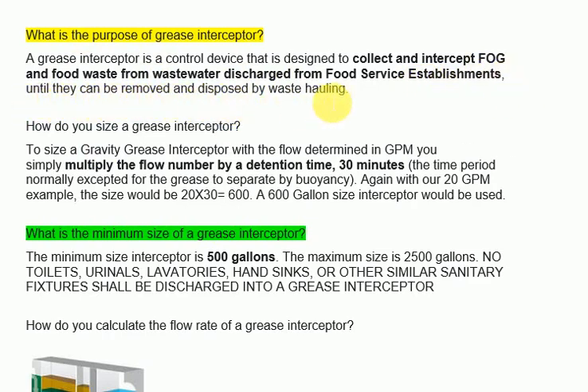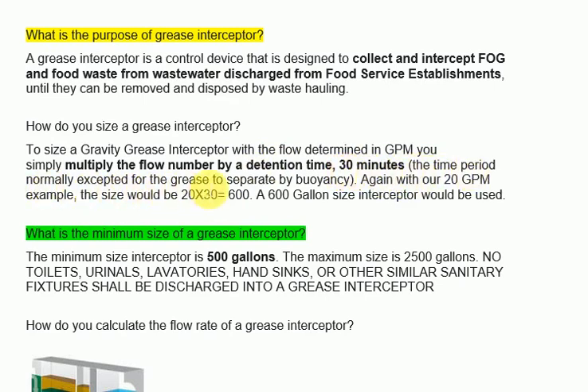How do you size a grease interceptor? To size a gravity grease interceptor with the flow determined in GPM, you simply multiply the flow number by a detention time of 30 minutes — the time period normally accepted for grease to separate by buoyancy. With a 20 GPM example, the size would be 20 x 30 = 600, so a 600-gallon interceptor would be used.